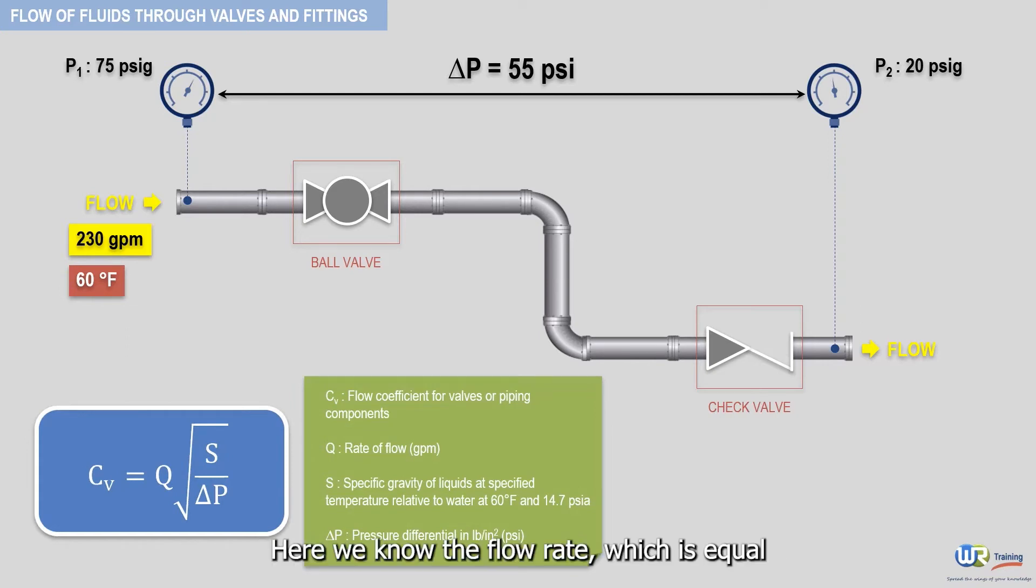Here we know the flow rate, which is equal to 230 GPM, and the pressure differential, 55 PSI. S refers to the specific gravity of the fluid. In our example, S equals 1, since the fluid is water.